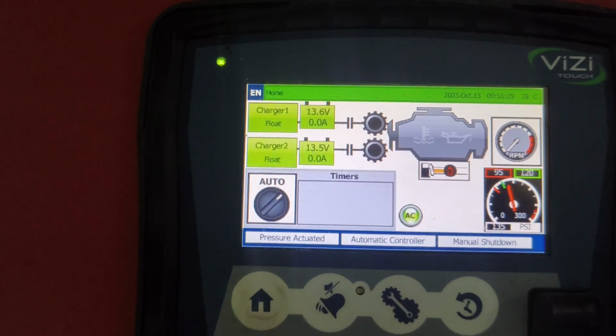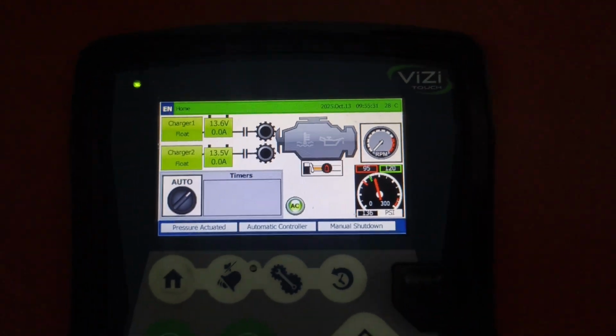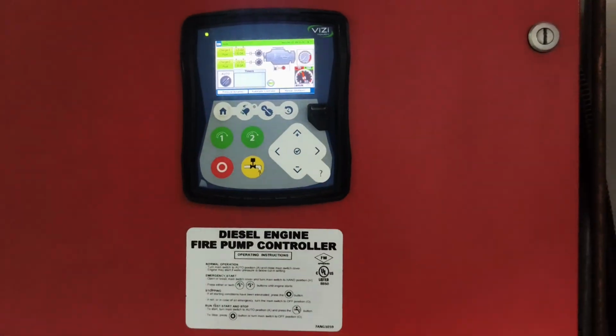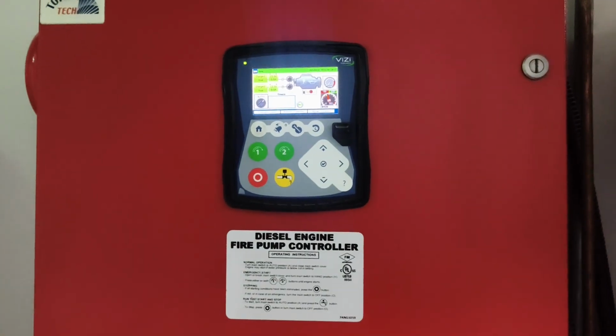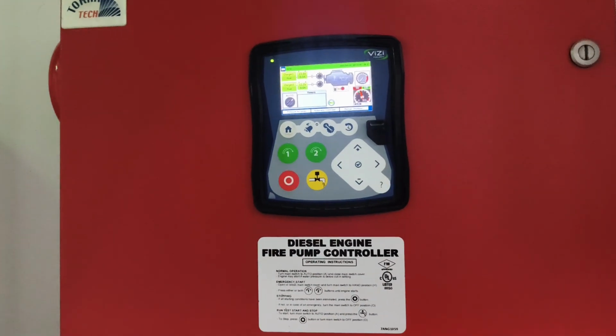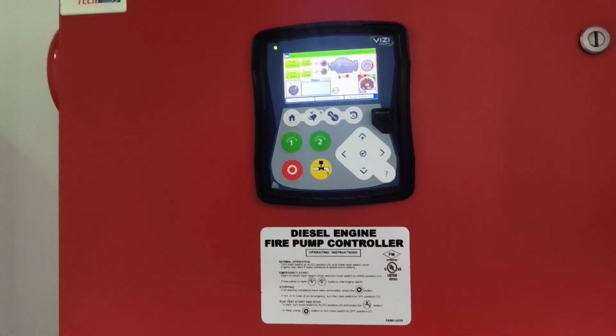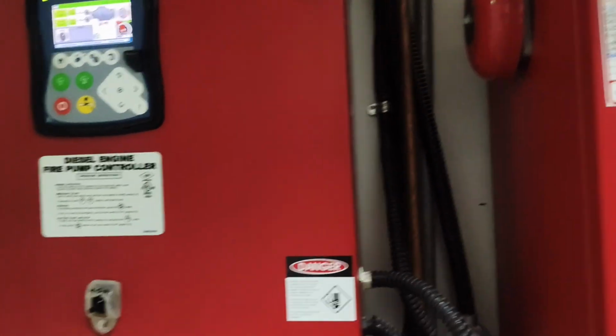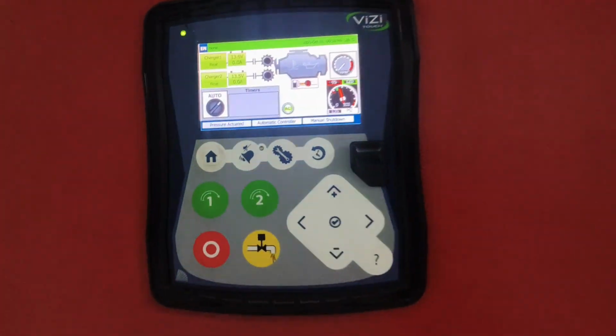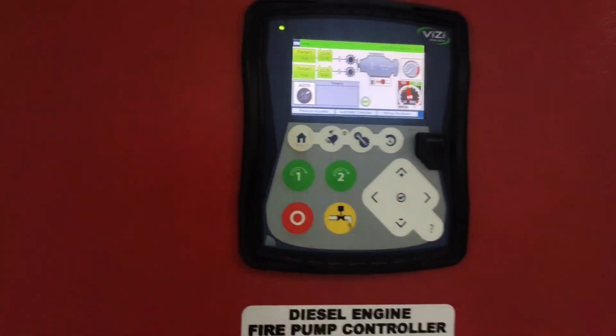So putting it in auto. Okay, now it's in auto. Before, when it was off, because of the interfaces connected, there was a signal inside the fire control panel showing the system in troubled condition. Now that this has been normalized, it's going to clear. This is basically why we need the interfaces.